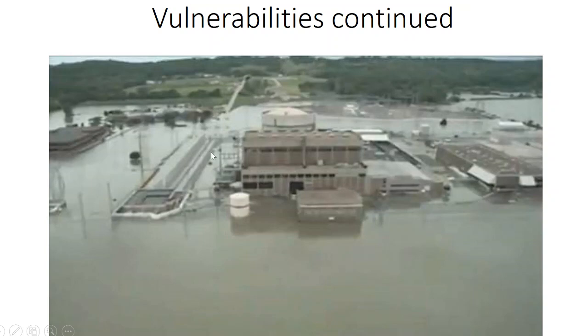Now, we had surrounded the plant with this Aqua Dam, and about a week before we got that Aqua Dam, we took some additional measures to add an alternate fill to our fuel oil tanks. Right here in the picture is about FO10, that's under about 3 feet of water. We put a standpipe on that for filling it. We also did it over here on FO1, which would be the fuel tank for our emergency diesel generators.